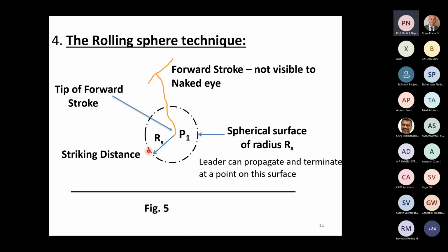So now this sphere tells us the region where the lightning is likely to strike. This principle can be used to protect buildings, and therefore we'll use this sphere to roll around the building to be protected, as we'll see a little later. So we call this technique the rolling sphere technique. Now, what's the principle? Basically, we'll assume that we want to give protection down to 5 kiloamperes.